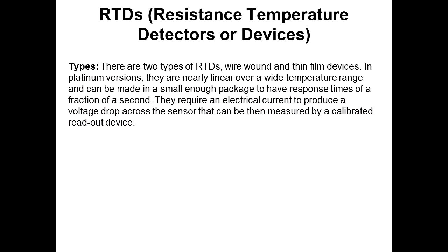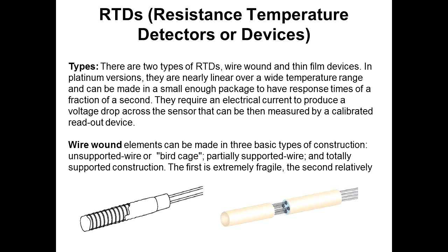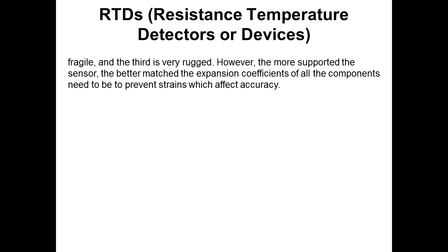Two types of RTDs, wire wound and thin film, are still being used widely, although thin film is taking over in the industry. It's much more rugged. You have a sensor that you're running an electrical voltage through and getting a differential back to a readout device. Wire wounds can be made in three basic configurations. Unsupported wire or bird cage, which is very fragile, but is used in what's called SPRT, specialized RTDs for calibration use. Partially wire supported and totally supported construction like this, where all the wires are supported by a ceramic or glass covering. The first is extremely fragile, the second relatively fragile, and the third very rugged.